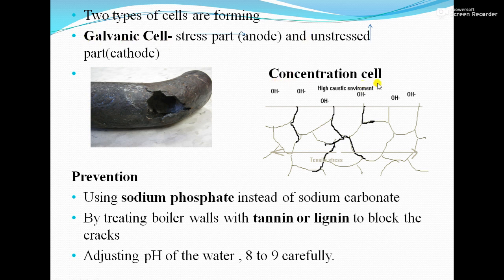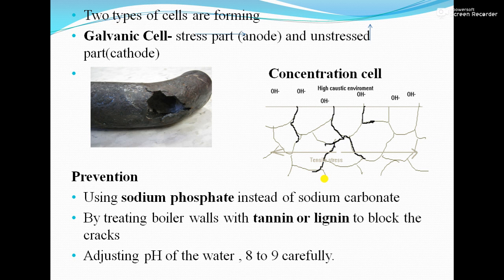The second cell is a concentration cell. NaOH present in the water penetrates through cracks by capillary action. This creates two regions: a higher concentration of NaOH at the surface and a lower concentration at the bottom. The region with higher NaOH concentration acts as the cathode and the lower concentration region acts as the anode, resulting in corrosion. This corrosion under highly caustic conditions is why it is called caustic embrittlement.